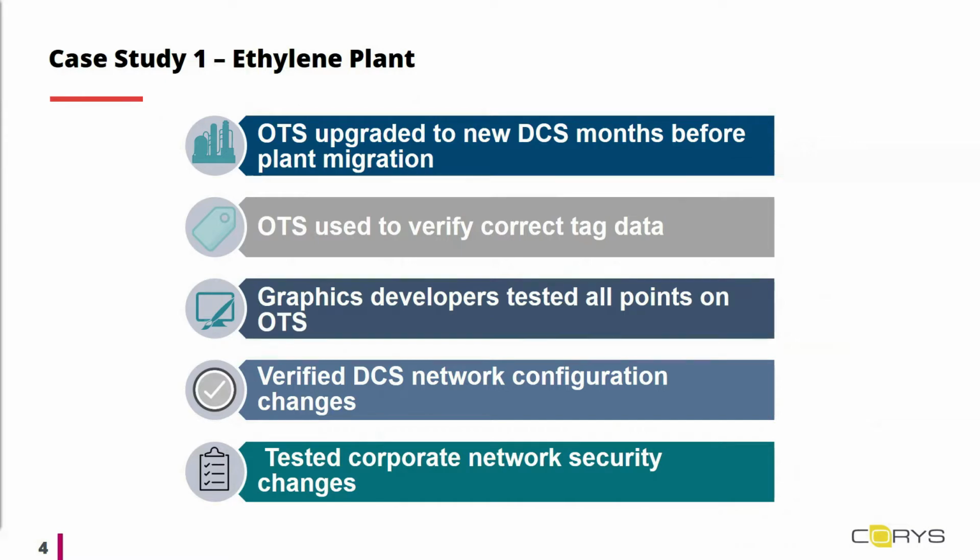Using the OTS, the client was also able to verify correct tag data, test the I/O points, verify DCS network configuration changes, and test corporate network security changes, all before going live in the plant.